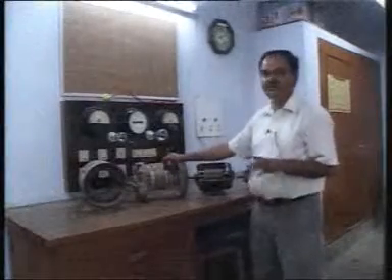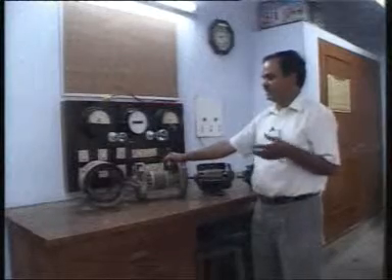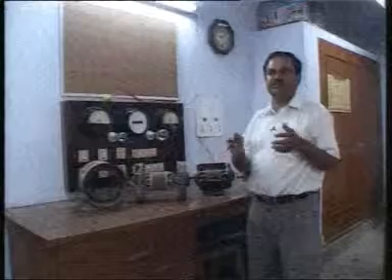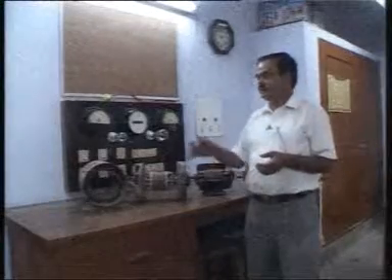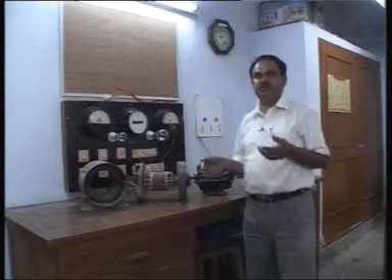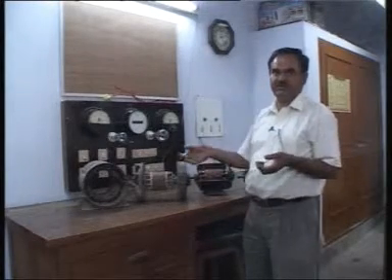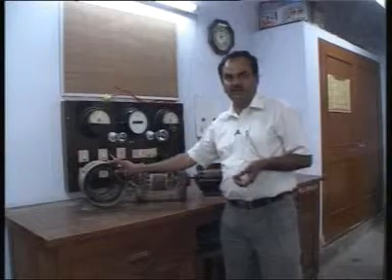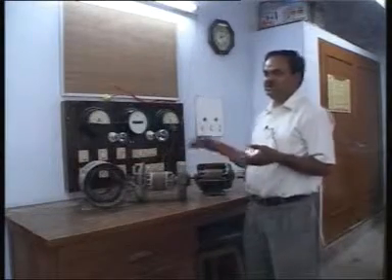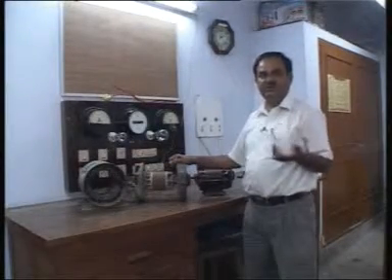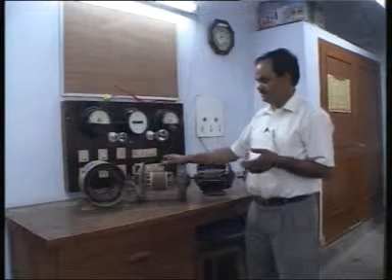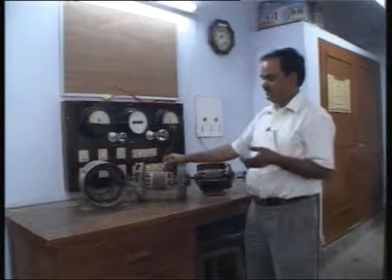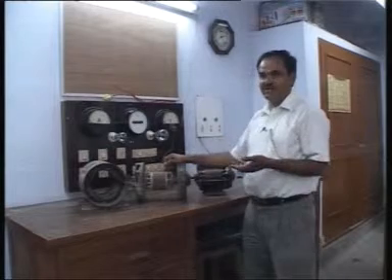This is the function of the centrifugal switch. A capacitor is also used to have a phase difference between the magnetic field produced by the starting winding as well as the running winding, so that we can produce a rotating torque which is not present if we are not using the starting winding. Depending upon this starting mechanism, different motors are available — if it is a capacitor start motor, we can say it is a capacitor start induction run motor.